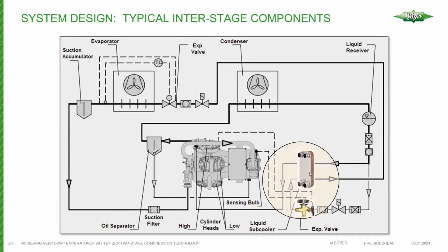Okay, so we have a brazed plate heat exchanger, you can see here in the circle, and then we have an expansion valve. And also BITZER provides the interstage kit, which includes the filter, the solenoid valve, and the sight glass. Okay, and then with the expansion valve, there's an orifice depending on the application, depending on the size of the compressor, and then we select the orifice, and that's included with the valve and with the compressor.